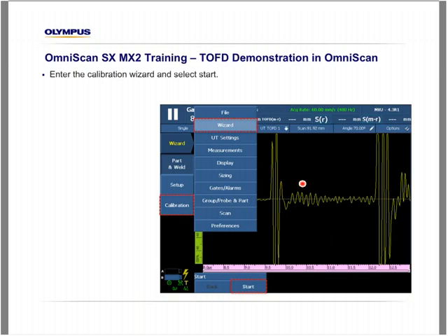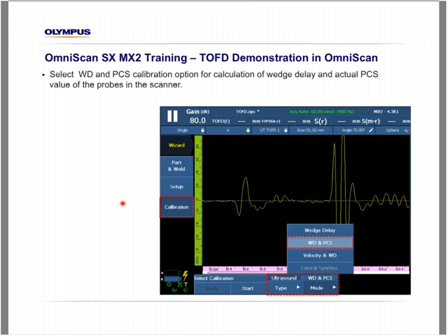The benefits I'll explain in analysis mode, but prior to setting the scanner on the pipe, we set the scanner on a flat block or pipe of known thickness, and by known thickness I mean not a nominal thickness, but something that was measured with mechanical calibrators, calipers, or a reference standard like an IIW block of known thickness.